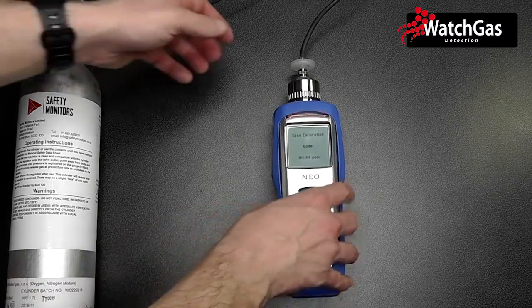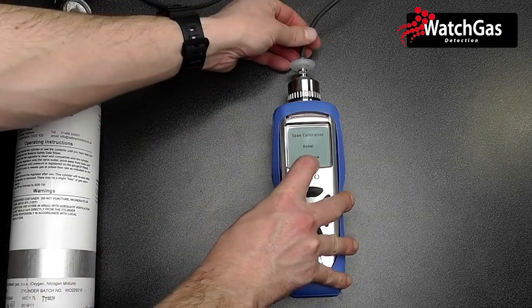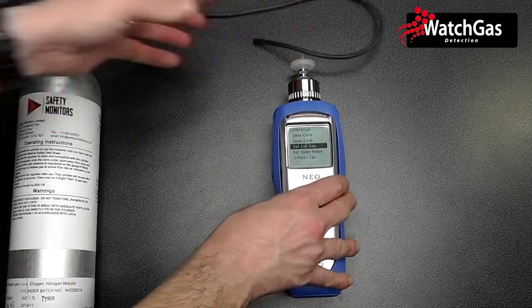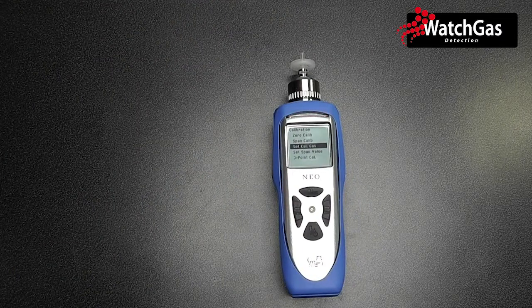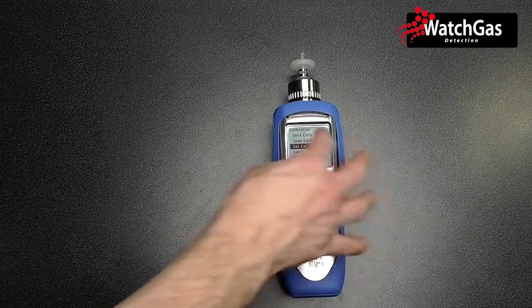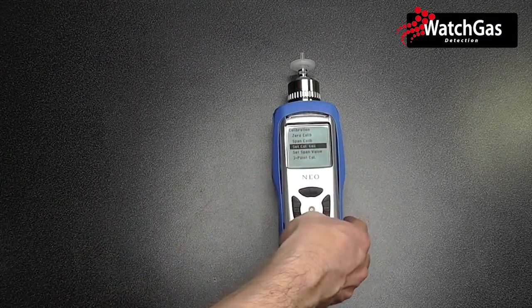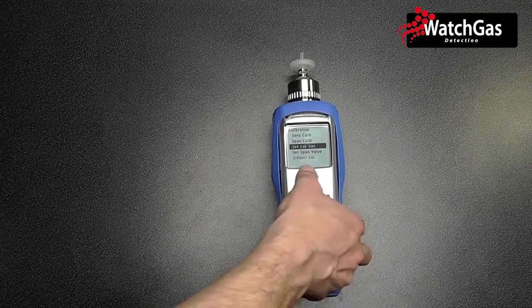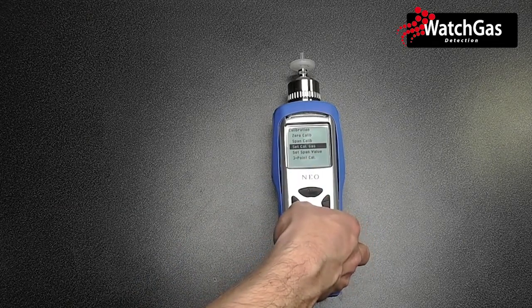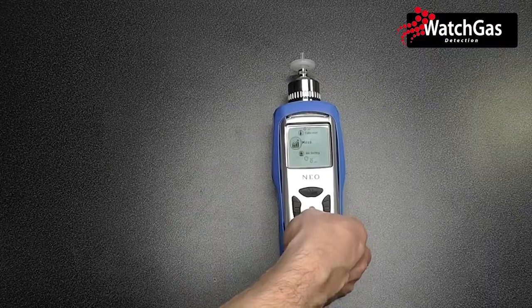We can see the calibration is done and we're getting a reading around 100 ppm. So we'll remove the gas. I can change to different calibration gases should I so wish, or different span values, or as I said, perform a 3-point calibration of looking at parts per billion. So if I press the escape button, I can come back out.